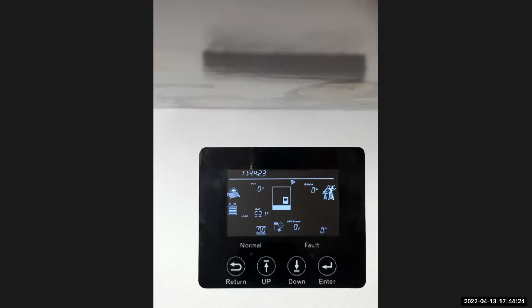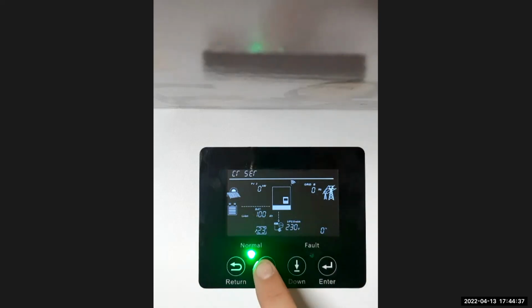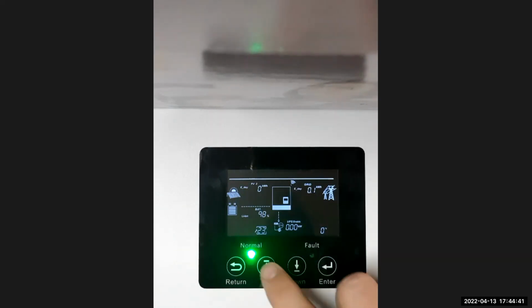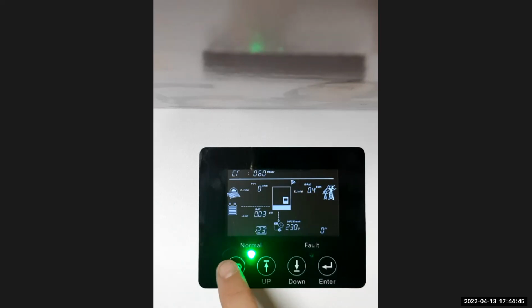Okay. It restarts again and you're done with that setting. And that's basically the settings that you'll be using on this inverter. That's parallel settings. That's for recording. That's for CT set. This setting doesn't do anything. It's for the hybrid one. You can't do anything on that one there.